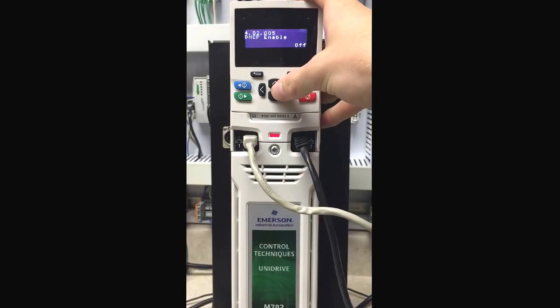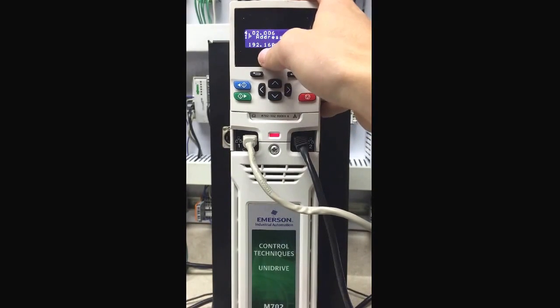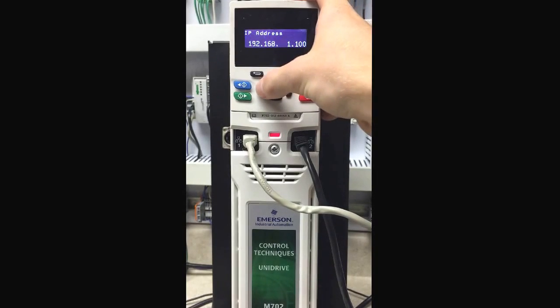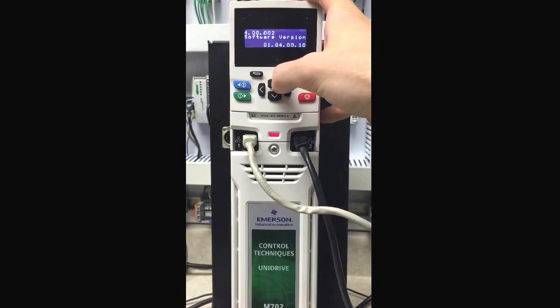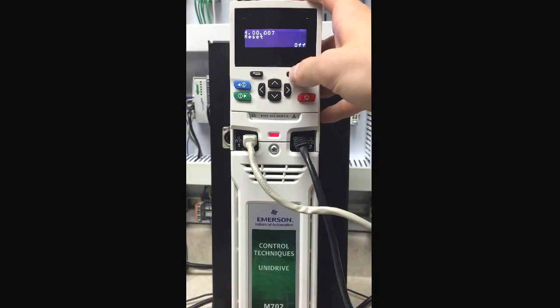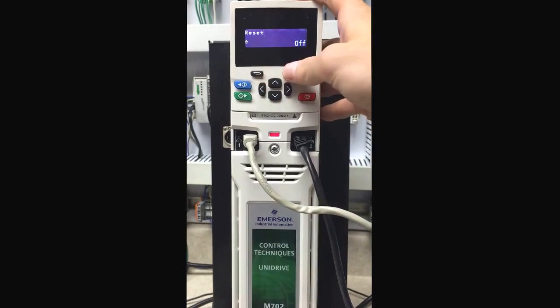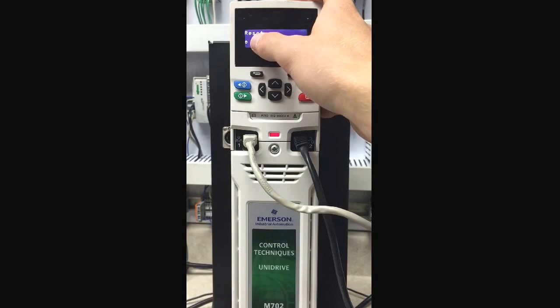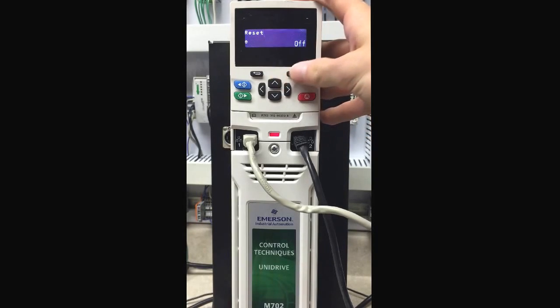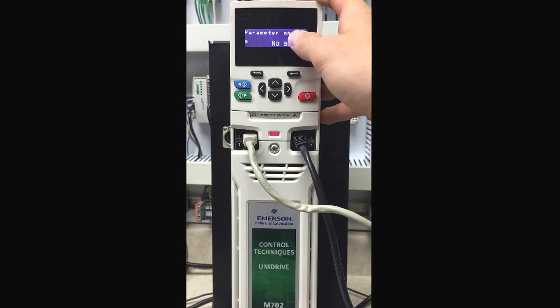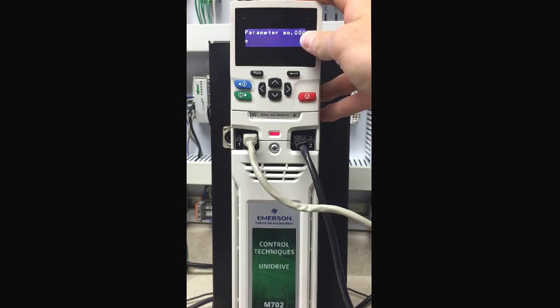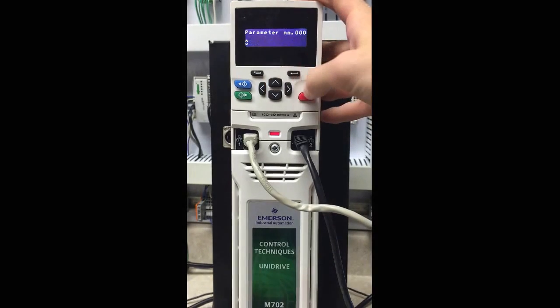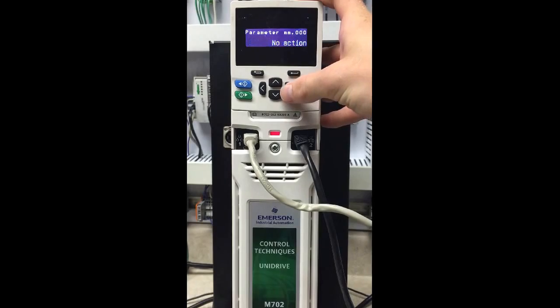We will have the drive set for 192.168.1.100. That's default. That's fine for this. We will now need to reset the slot 4 module. So we will go to menu 0, parameter 7, and turn this to on. This will automatically toggle back to off and take you to menu 0, parameter 0. Now we will save our parameters, save our changes.